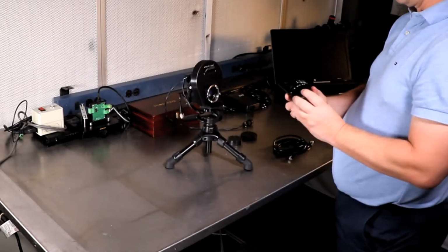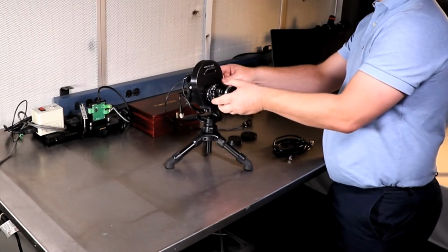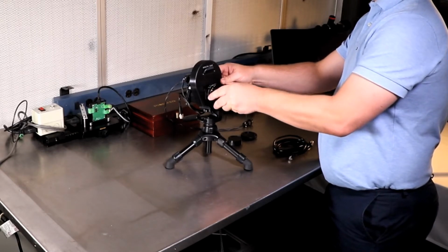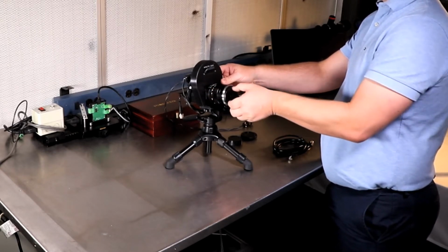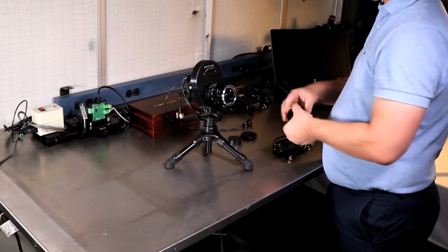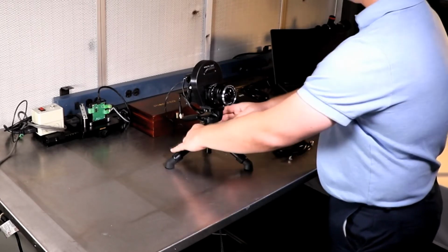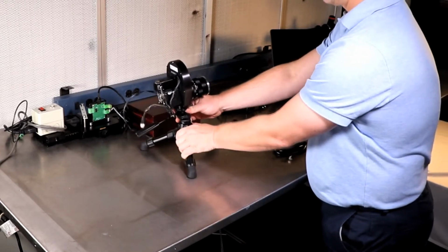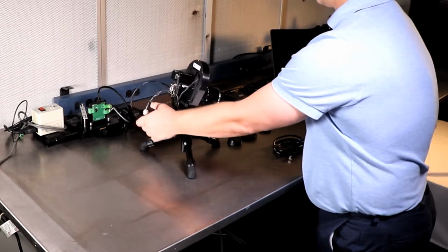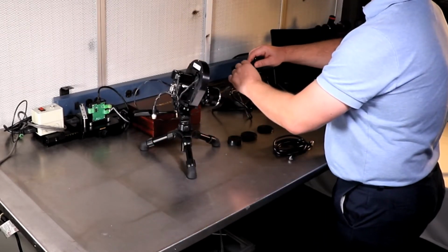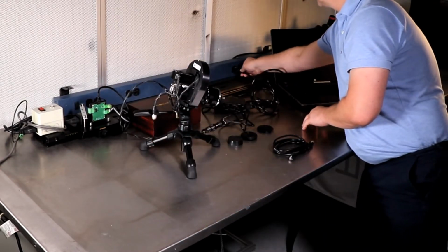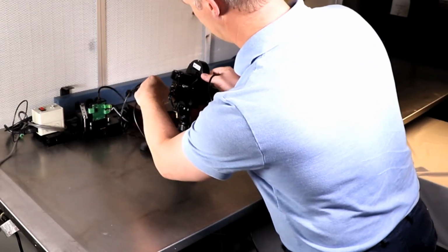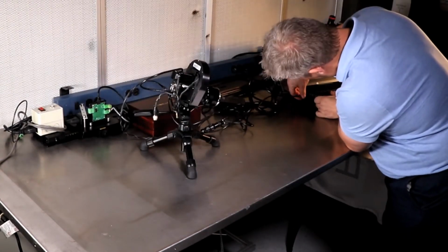You will now need to connect a lens to the front of the device. SpectroCam cameras are compatible with standard F-mount optical interfaces. A range of appropriate lenses and adapters, such as those for microscopes, are also available. Next, connect the motor and power. Run the Ethernet cable to the SpectroCam device and laptop.